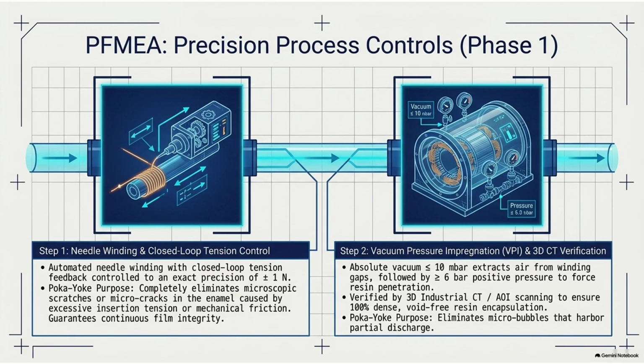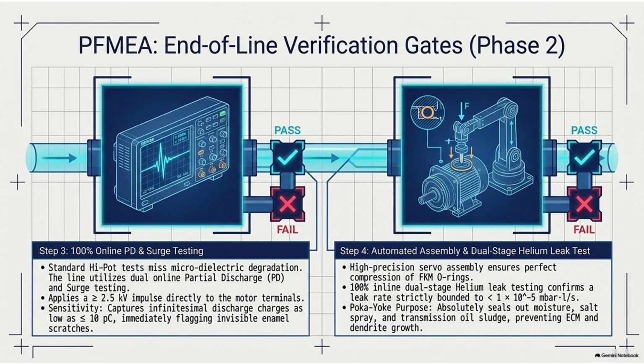Right. And they also use custom 3D preformed paper at the ends of the motor to physically separate the different phases of wire from touching each other. So they are eliminating any geometric path the electricity could possibly take to short out. Exactly. But the most elegant design solution in the DFMEA isn't just about building thicker walls. What is it? It's about disarming the weapon itself. Okay, color me intrigued. We established that the root cause of the partial discharge sparks is the incredibly fast switching speed of the silicon carbide inverter, right? Right, the 10 kilovolt per microsecond voltage spike.